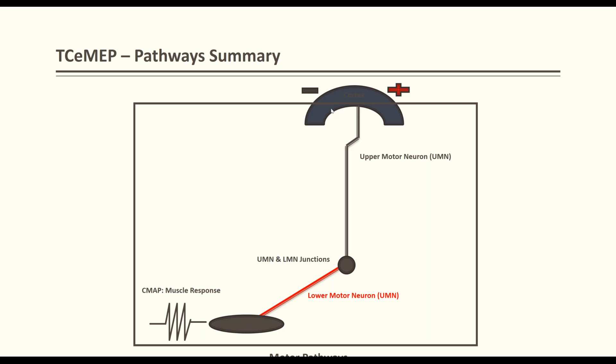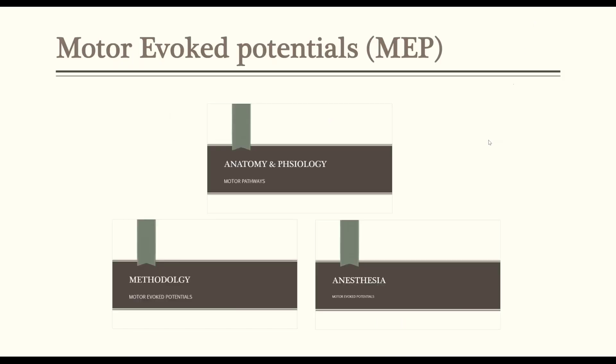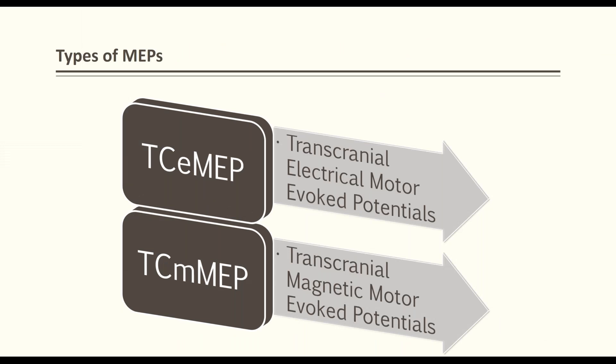When setting up, the muscles recorded must be on the side opposite to the anodal electrode, not the cathodal side. For the Cadwell machine, black should always be on the left and red on the right. C2 and C4 should always be on the red output — stimulating in normal mode gives a response from the left side, and reversing polarity gives a response from the right side. There are two types of MEP: transcranial magnetic (TMS) and transcranial electrical.